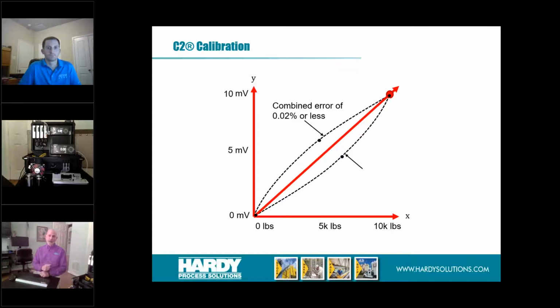And what that means is that our load cells are matched. So if I'm in the middle of a batch and I decide that I've got a bad load cell, instead of throwing that batch out, I can change out my load cell and still have a good bit of accuracy because of the matched load cell. And then after the batch is over, I can do my calibration and zero the scale and have a really well-calibrated scale at that point. I'm going to show you in a slide a little bit later some of the details of exactly what I'm talking about when we combine all the slopes of the load cells.